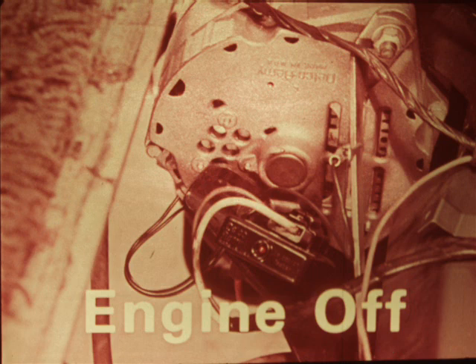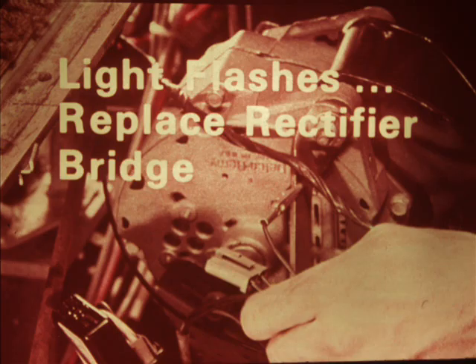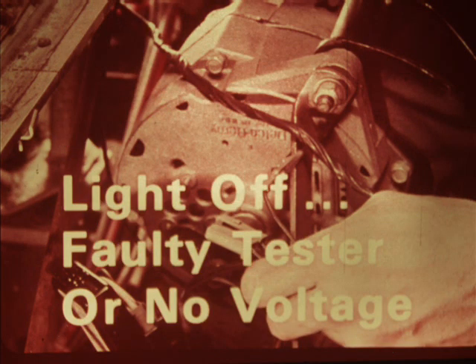With the engine off, plug the generator connector into the tester and plug the tester leads into the generator. Ground the tester on the generator frame. If the tester light comes on and remains on, it indicates that the tester itself is faulty. If the tester light remains off, pull the tester connector plug from the generator. If the tester light then flashes, you should replace the rectifier bridge. If the tester light remains off, either the tester is faulty or no voltage is getting to the tester, probably because of a broken or faulty connection.